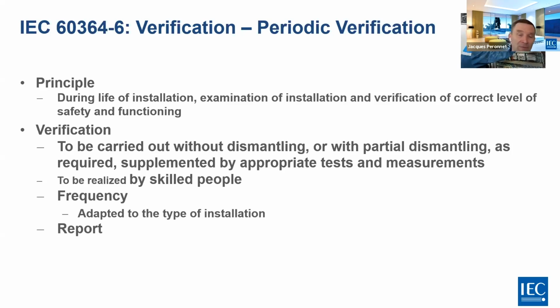And then it's important also that during the lifetime of the installation, you make a periodic verification, which is an examination of the installation and the verification of the correct level of safety and functioning. So verification has to be carried out without dismounting or with partial dismounting as required, supplemented by appropriate tests and measurements.